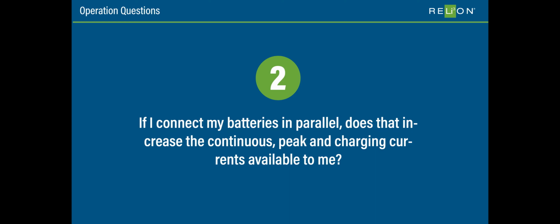The internal resistance of batteries—with all batteries, but specifically lithium, it's no different—means the current's not shared evenly, and we want to caution people against doing that because we don't want you to harm the BMS. So we suggest that you derate: double it, and then multiply by 75% to get your max values for continuous peak and charging.